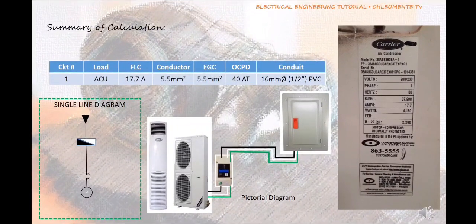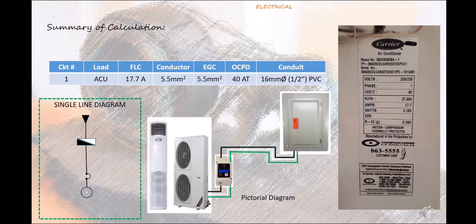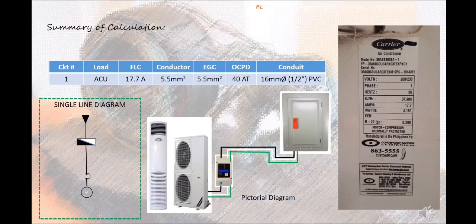Here is the summary of our calculation showing the schedule of loads, single line diagram and pictorial diagram. Circuit breaker is provided near the outdoor unit for easy access during troubleshooting, repair and maintenance. Equipment Grounding Conductor (EGC) in green colored wire is also provided for safety during ground fault.